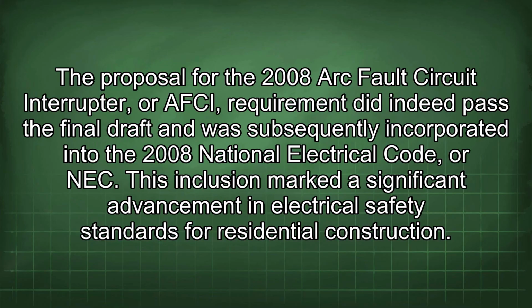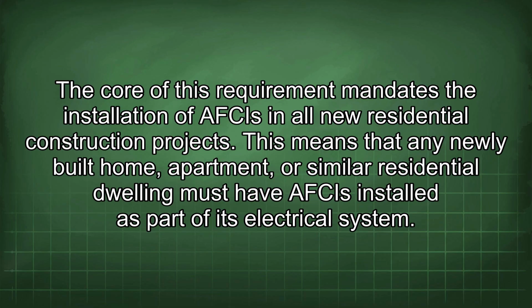Proposal for the 2008 ARC Fault Circuit Interrupter, or AFCI, requirement did indeed pass the final draft and was subsequently incorporated into the 2008 National Electrical Code, or NEC. This inclusion marked a significant advancement in electrical safety standards for residential construction. The core of this requirement mandates the installation of AFCIs in all new residential construction projects.